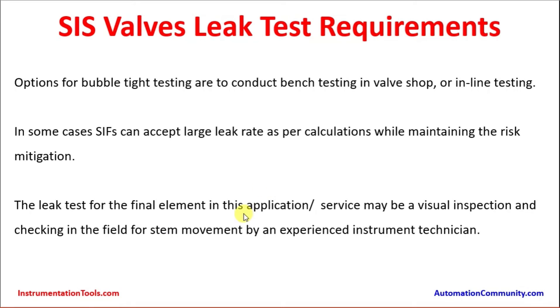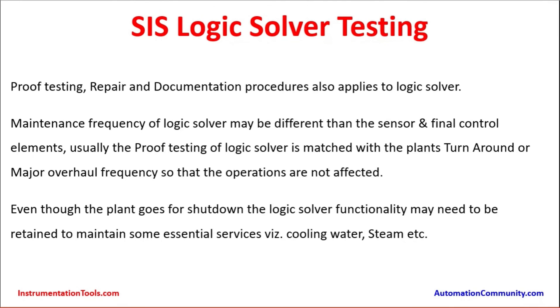Leak testing for the final element in this application service may include visual inspection, checking, and field testing for stem movement by an experienced instrument technician with good experience.